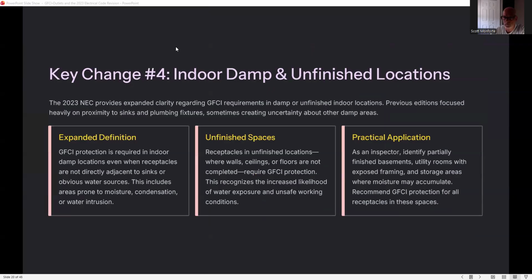Key change number 4, indoor damp and unfinished locations. The 2023 NEC provides expanded clarification regarding GFCI requirements in damp or unfinished indoor locations. Previous editions focused heavily on proximity to sinks and plumbing fixtures, sometimes creating uncertainty about other damp areas. Expanded definition: GFCI protection is required in indoor damp locations, even when receptacles are not directly adjacent to sinks or obvious water sources. This includes areas prone to moisture condensation or water intrusion.